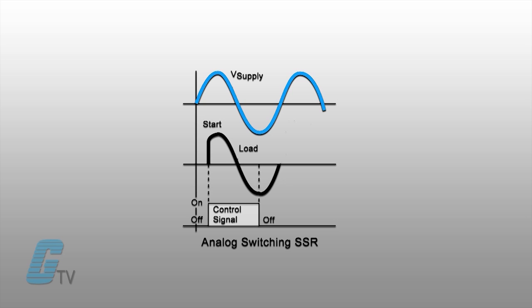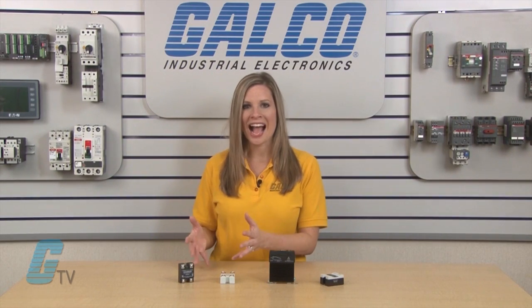Analog switching relays have an infinite number of possible output voltages and are proportional to the input voltage or current. An analog switching relay has a built-in synchronizing circuit that can achieve phase angle control. These relays can be ideal for soft starting or limiting high inrush current.